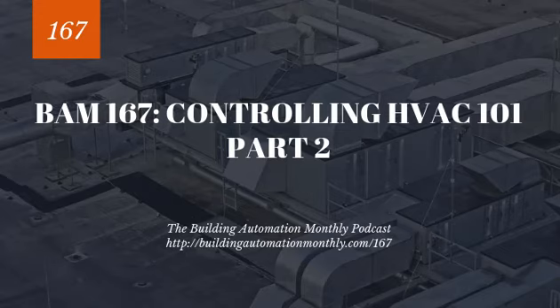Now, the thing is, with mixed air units, we introduce some new control strategies. Whereas with outdoor air units and rooftop units, we tend to be controlling either to zone temp or discharge air, with mixed air we introduce mixed air temperature control, especially if we're utilizing economizers. So we'll have a mixed air temperature sensor and we'll drive economizer control. And then we have outdoor air damper minimum position reset. And this is typically fed by either CO2 or mixed air temperature control PID loops.